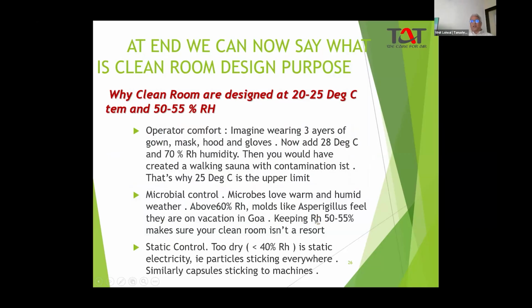Then microbiological control. Microbes love warm and humid weather. At about 60% RH, microbes like Aspergillus feel they are on vacation in Goa. So keeping the RH at 50 to 55 makes sure your clean room is not a resort for them. And static control: if it's too dry, static electricity will be there, so particles will stick everywhere, like capsules sticking to machines.